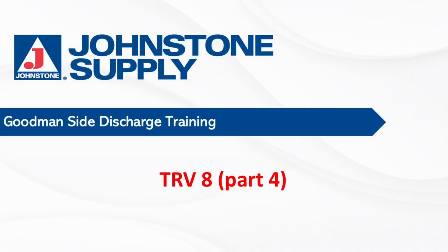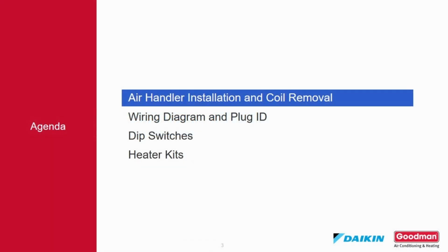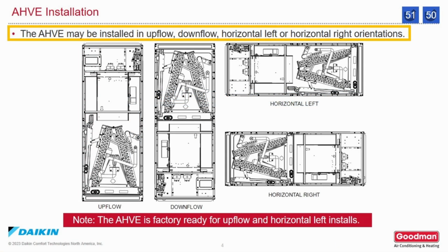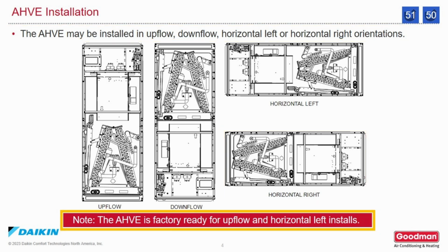Goodman Side Discharge Installation and Commissioning Technical Training Module, TRV 8, Part 4. Air Handler Installation and Coil Removal. The AHVE air handler may be installed in an upflow, downflow, horizontal left, or horizontal right orientation. Please note that the air handler is factory ready for upflow and horizontal left installations.